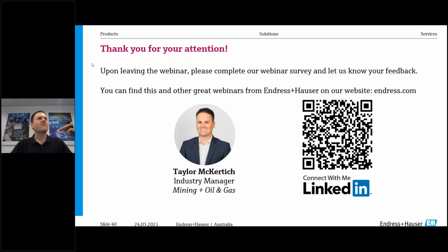He asks, can the meter health parameter be seen using an Netilion system? Yep, thanks, Rod. That's a great question. You can bring heartbeat information, or the other variables, the HSBI heartbeat variable, into an Netilion. We can send you some further information about how to bring that in a bit later. It is an important thing, because an Netilion, for those that might not know, is the IoT solution from Endress+Hauser. The great thing about that is you can bring a lot of the information from the field into your cloud solution, and it can be used for monitoring or for preventative maintenance as well. That's a great question.